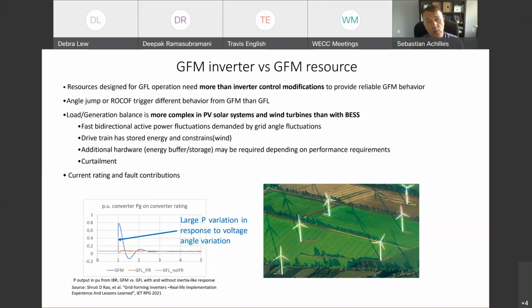We will try to avoid curtailment, but that's another option. Or potentially, we may need to add hardware like energy storage to handle the fast power demands, whether injection or absorption. So to have a grid-forming wind turbine or a grid-forming solar resource may require more than just changing the inverter, and that is defined quite a bit by how much power, in the case of an angle shift, will be required. So the details of what the grid-forming resource has to do will determine if you need to add more hardware or not.